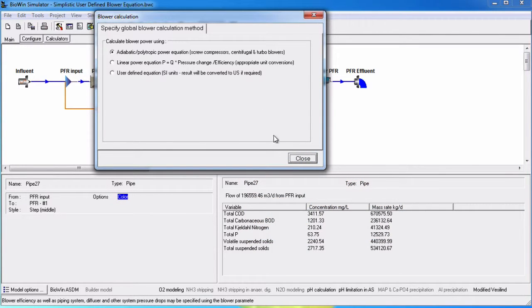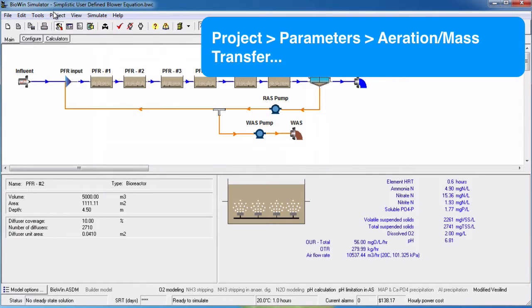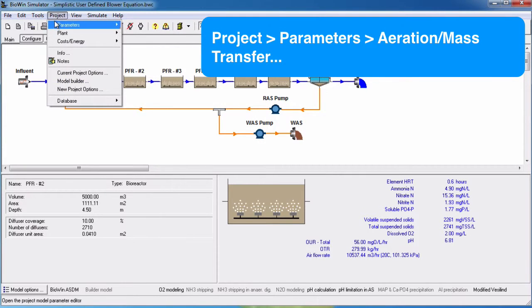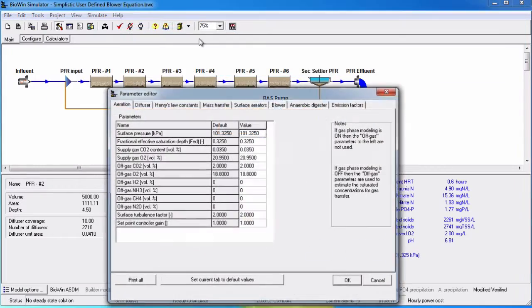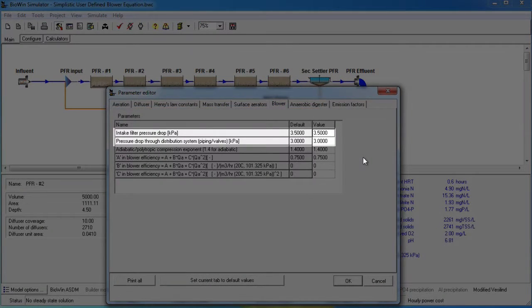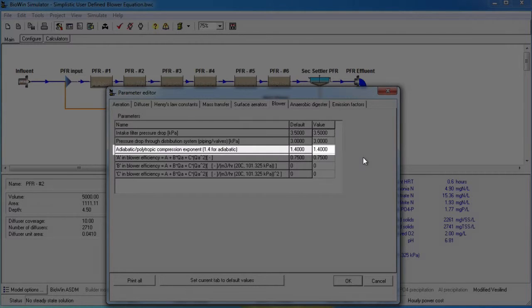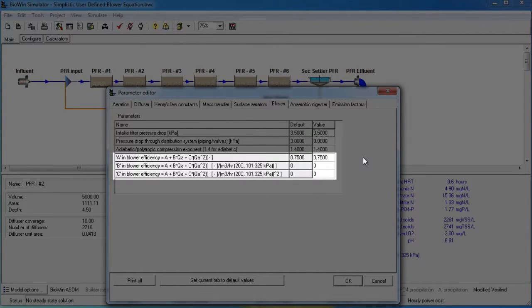Global blower parameters can be specified under Project, Parameters, Aeration Mass Transfer, and the blower tab. This is where we can indicate pressure losses through the air delivery system, the adiabatic polytropic compression exponent, and blower efficiency which can be set up to vary with airflow.